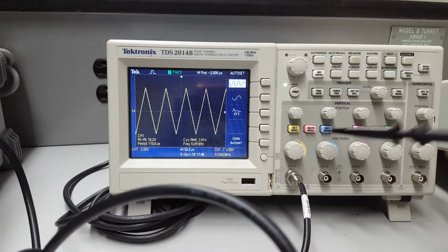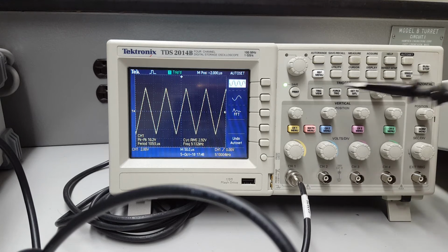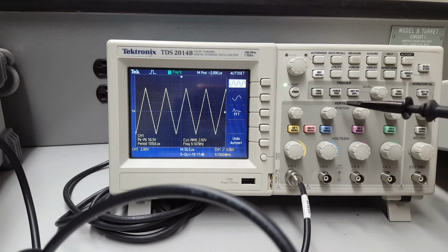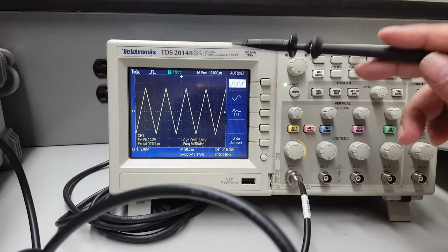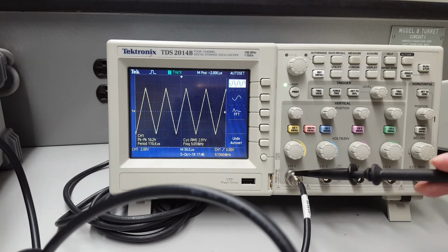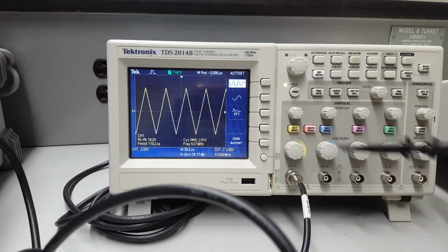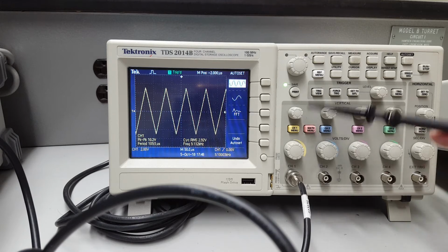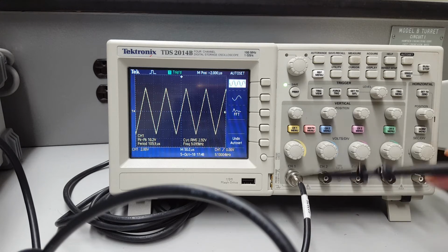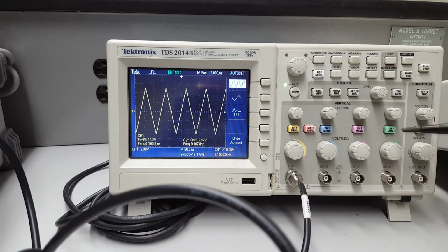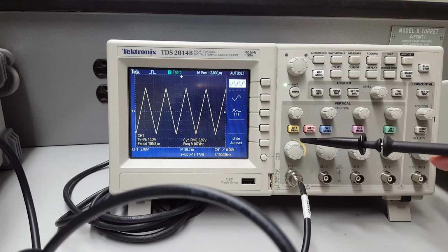And then here, what I have is the vertical axis. These are things that have to do with the vertical axis. But I'm measuring 4 signals at one time, so each signal will have its own keyboard. This here will be for channel 1, this for channel 2, this for channel 3, and this for channel 4. The most important thing we're going to look at is this knob. This big knob here is what we call voltage per division.